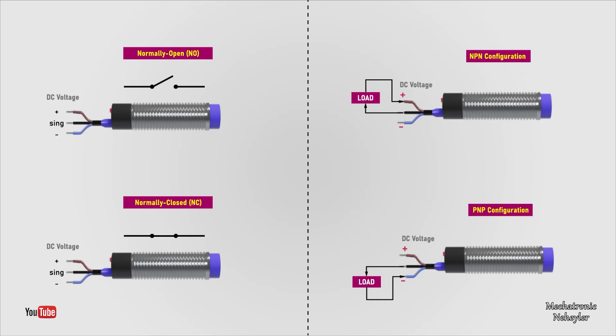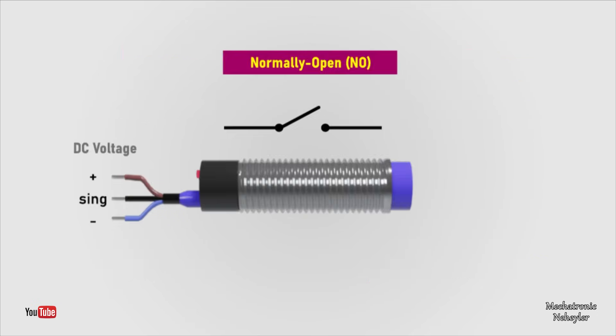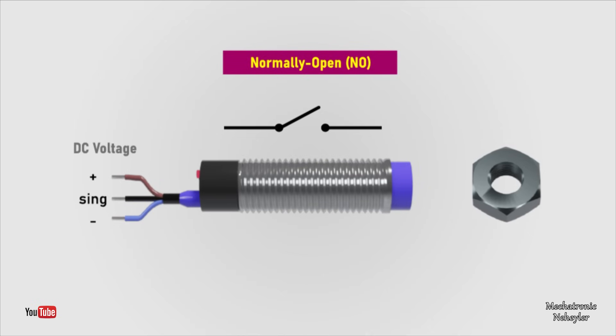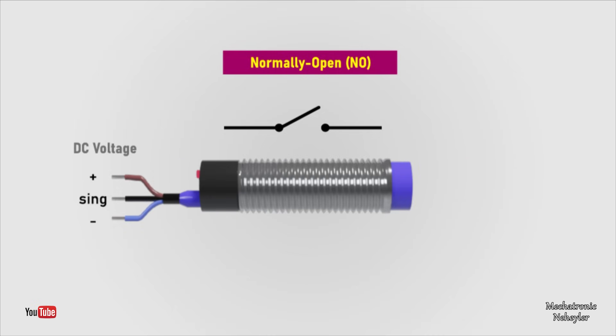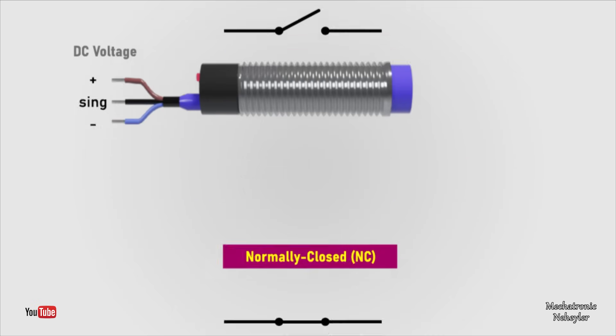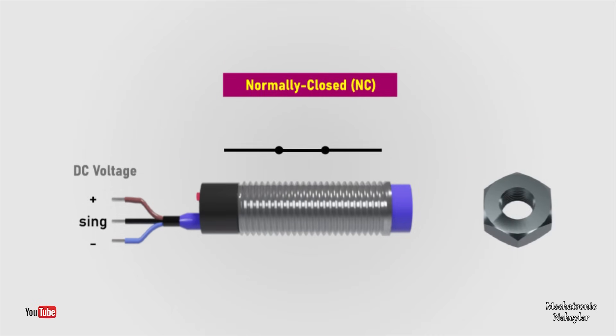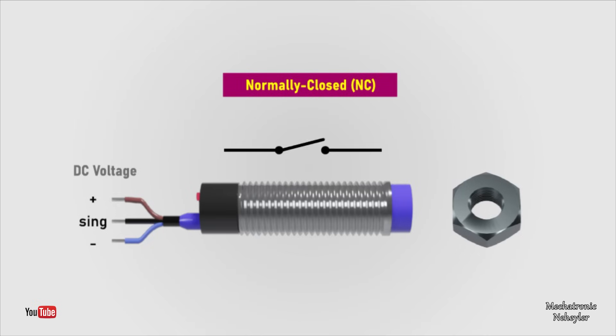There are also other settings. A sensor can be normally open or normally closed. If a metallic object approaches the normally open sensor, it detects the object and closes its contact, sending a high-level signal to its output. If a metallic object approaches the normally closed sensor, the sensor detects the object and opens its contact, sending a low-level signal to its output.